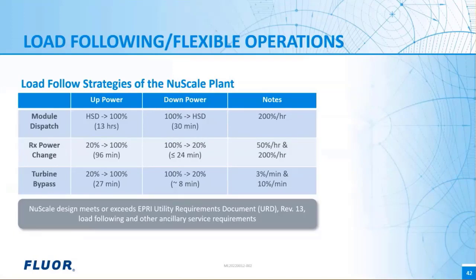And namely, the NuScale small modular reactor has three load following modes. First, for longer term load following, you have module dispatch, where individual modules can be shut down or started up. And you can see how quickly that can be done on this slide. For the medium-term disruptions, let's say for an hour to a week, you can up or down power the individual modules, and that's the reactor power change line item. And then for very short-term transients, like the grid trips momentarily, you can go to that turbine bypass that I already described.